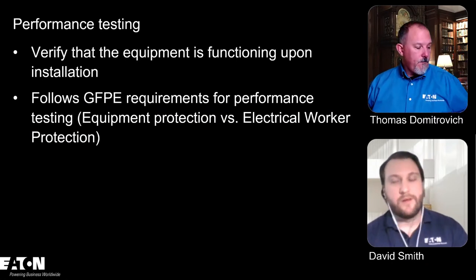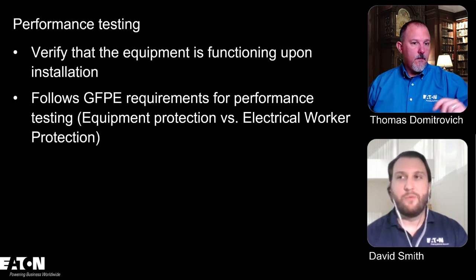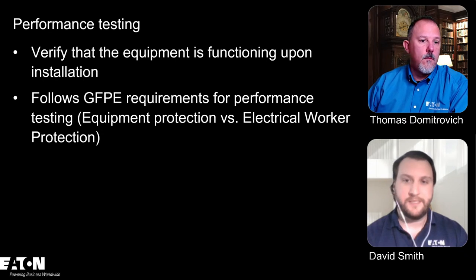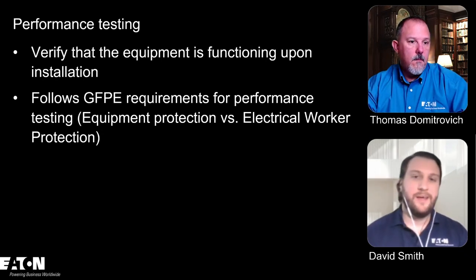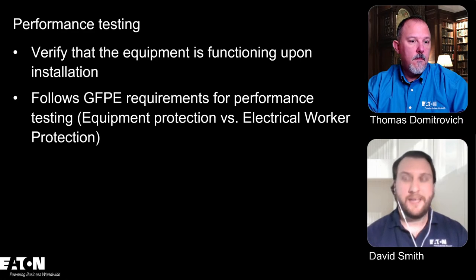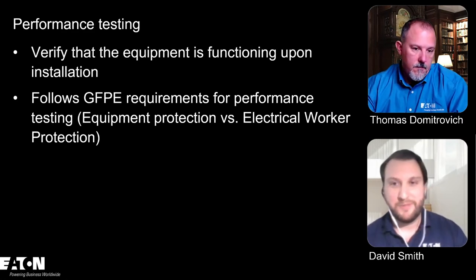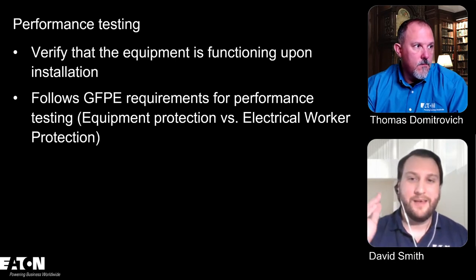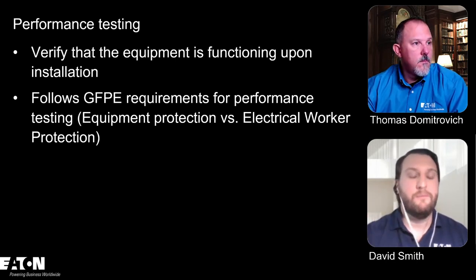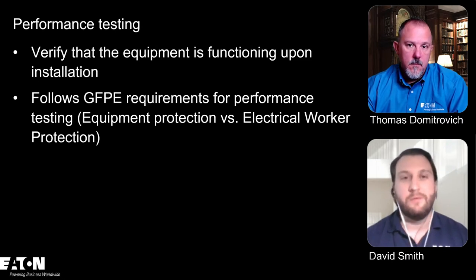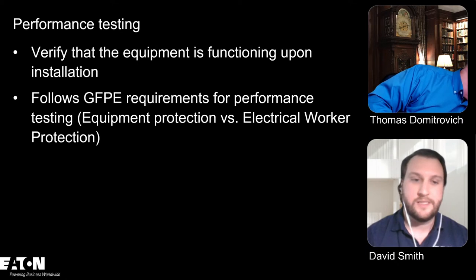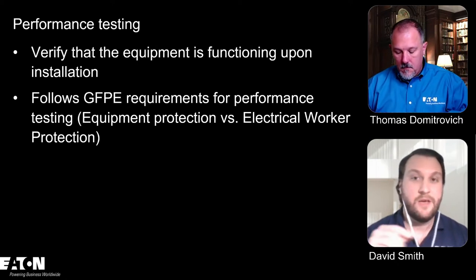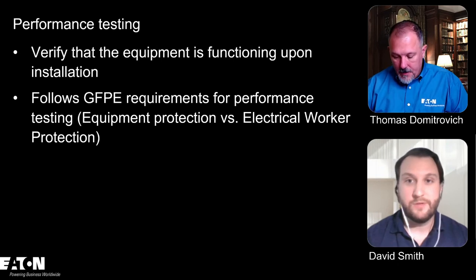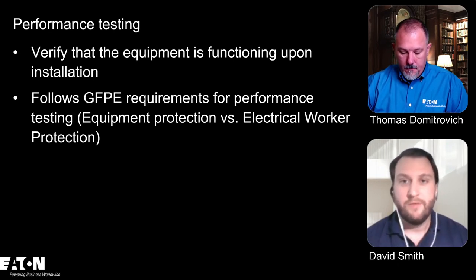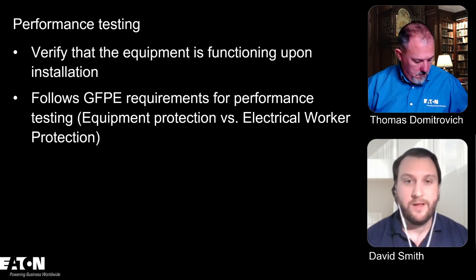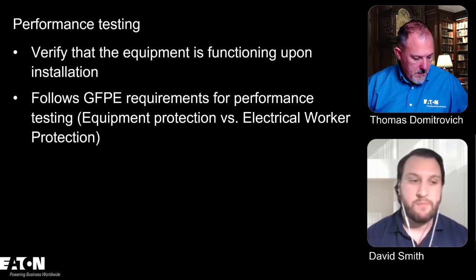Sure. So particularly whenever it comes to performance testing, it's a little bit more complicated on the sister article of 240.67 because you're talking about fuses. It's particularly difficult to test a fuse, because if it works, then you have to replace the fuse. Whenever we're talking about 240.87 for circuit breakers, there's a little bit more of an understanding that you could probably test it. Specifically in the 2020 NEC, the performance testing is, I believe, entirely new language.